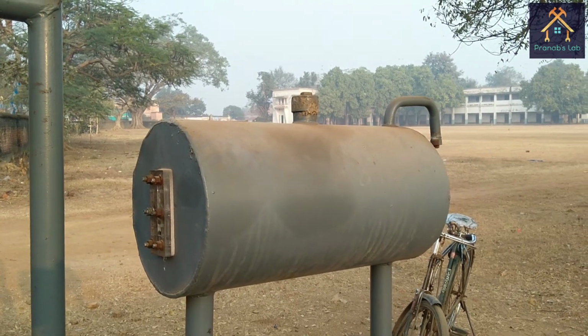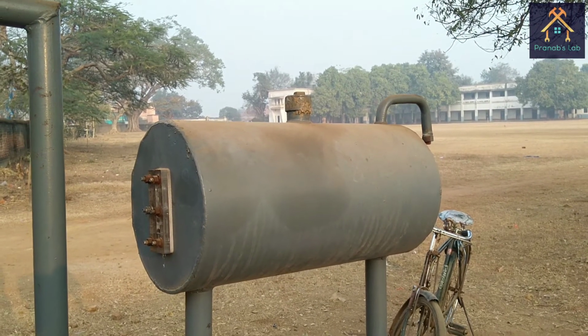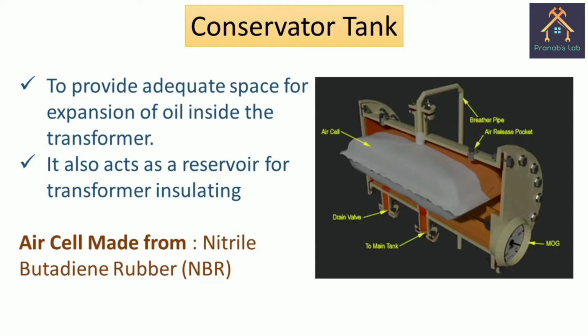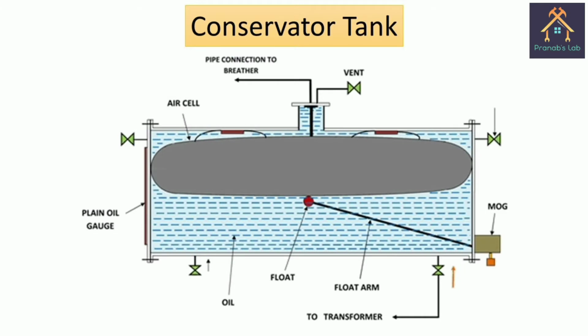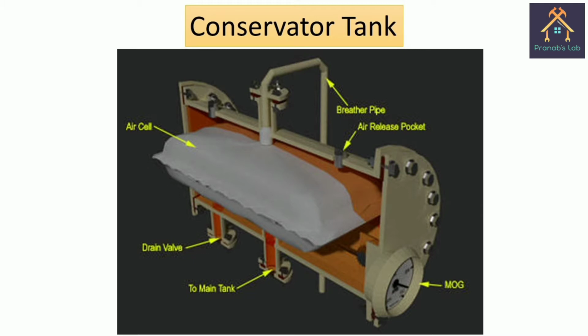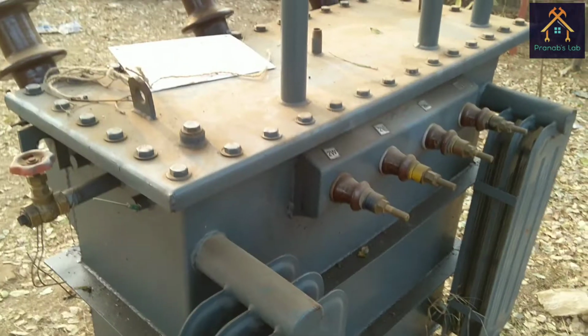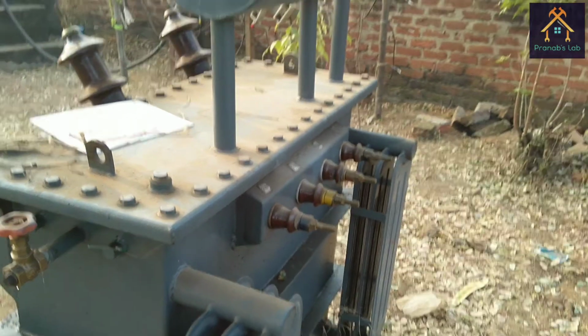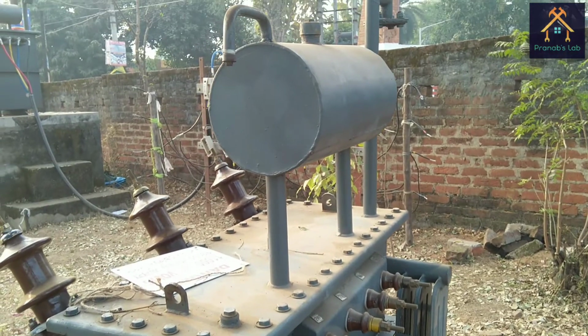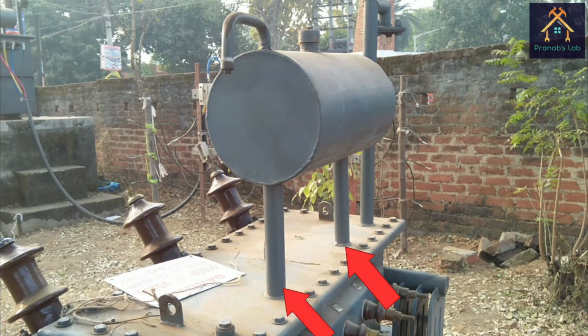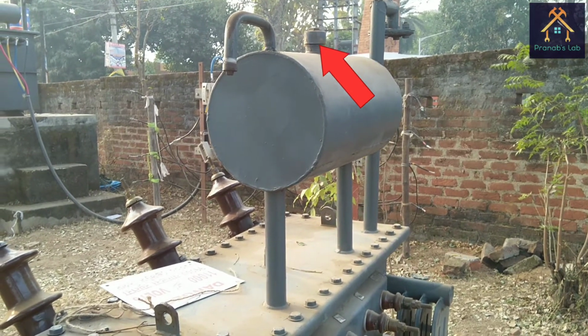The conservator tank is used to provide adequate space for oil expansion inside the transformer. The tank also acts as the reservoir for the transformer oil. I will explain the full operation of it in another video. Here you can see there are 4 pipes fitted with the conservator tank. The 2 vertical pipes are directly fitted with the transformer main tank, and the right angled bend pipe is to be fitted with the breather, and the topmost pipe is for the oil inlet purpose.